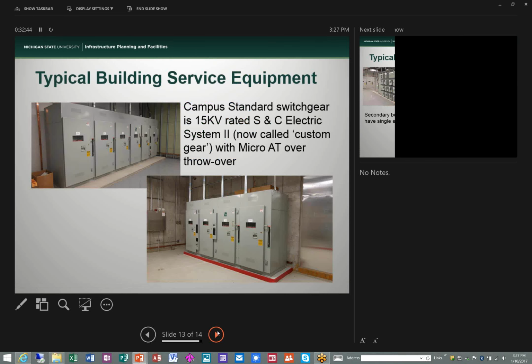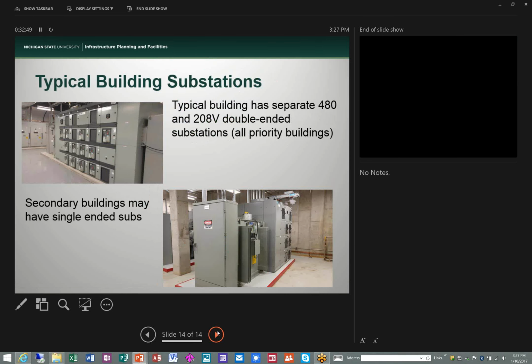And then here's a picture. The upper left is the newest building on campus, which is the bioengineering research building. That's the 480 volt substation. And then on the lower right is the 208 sub for the IM Circle complex. That gives you a sense of how we distribute and how we're configured in each of the buildings. The priority buildings, as noted, have separate 480 and 208 subs, and they're double-ended for the secondary selective.